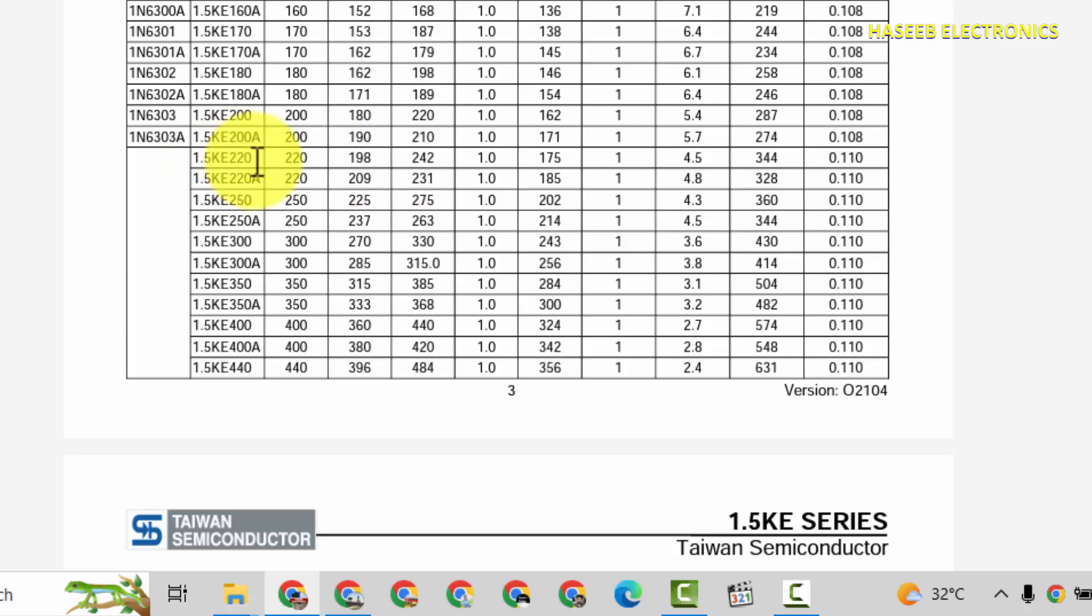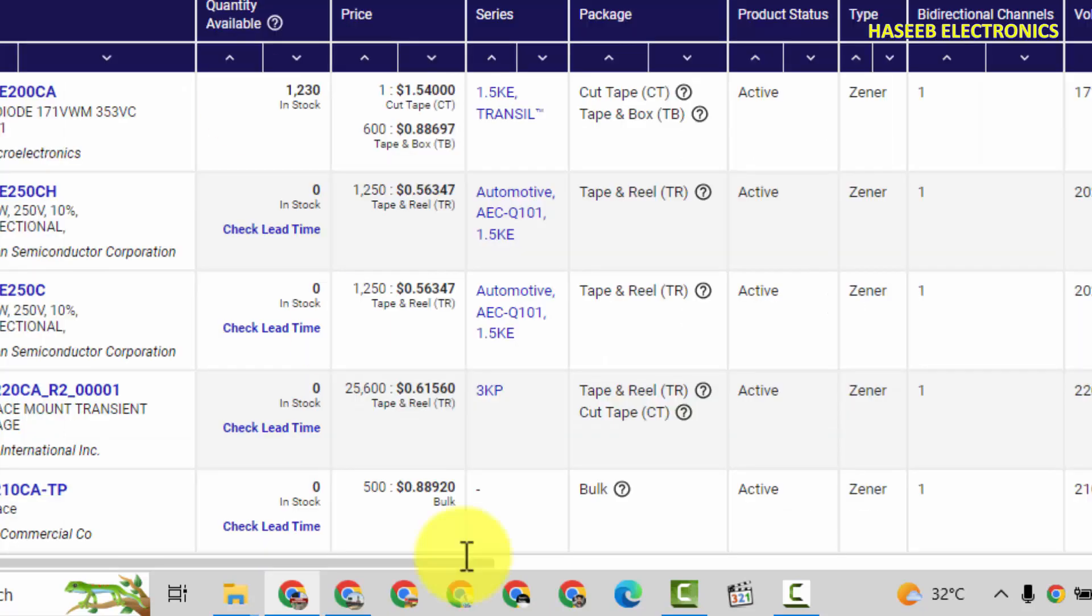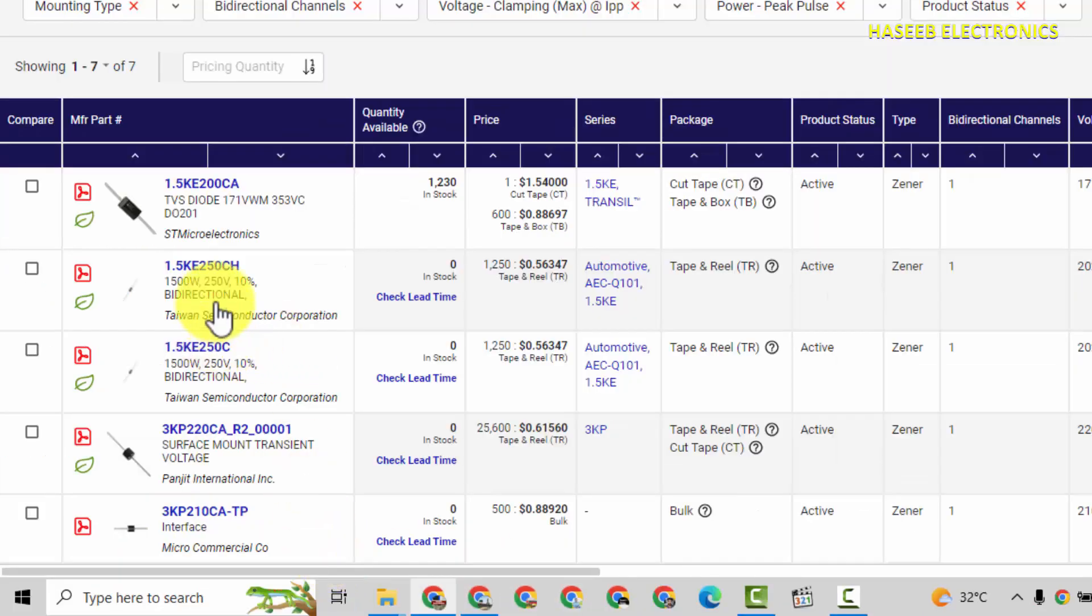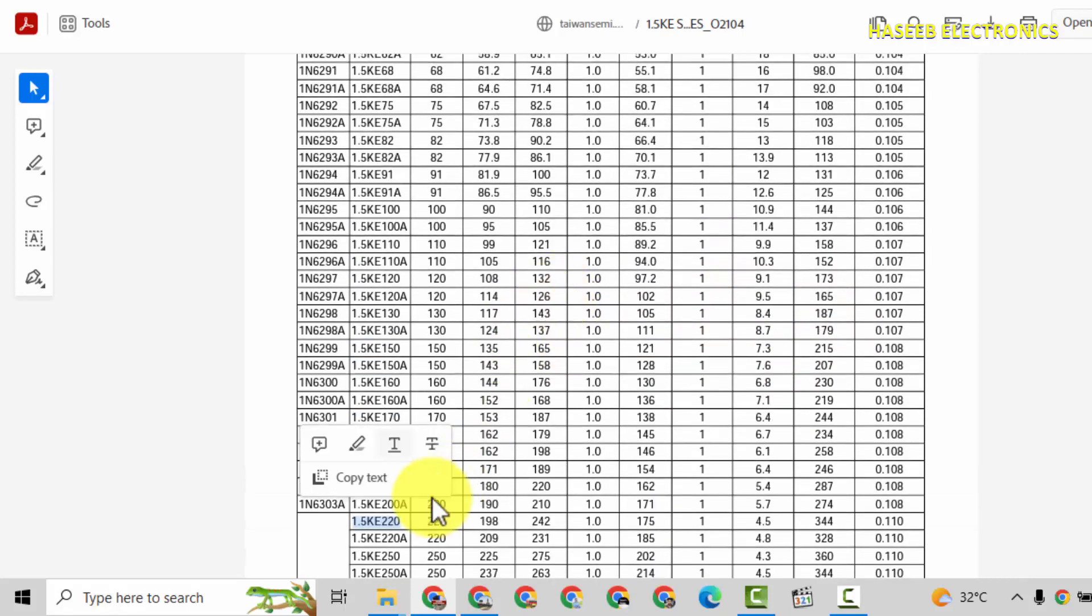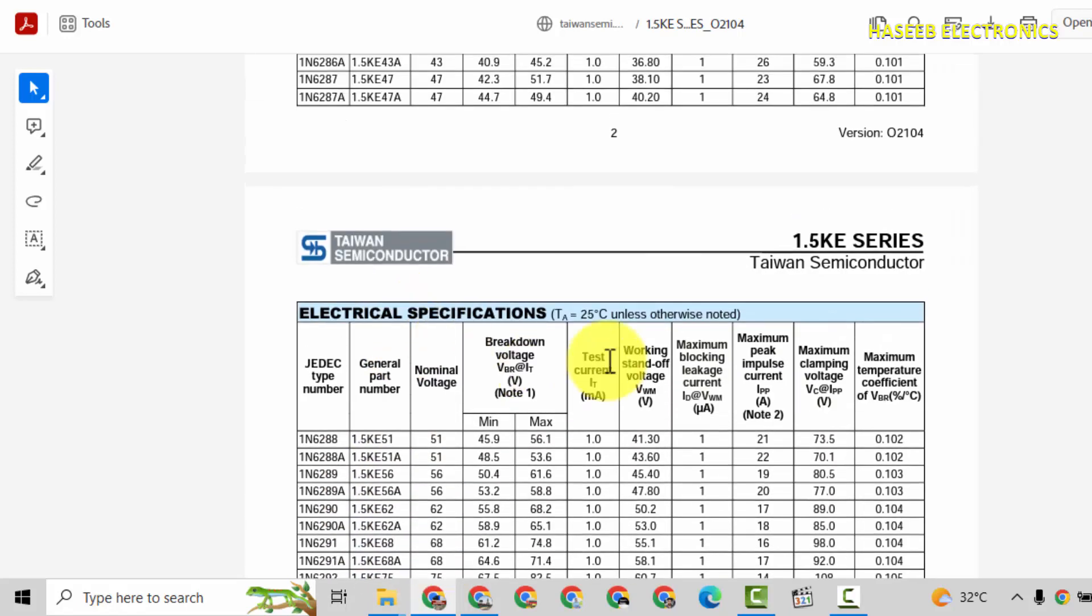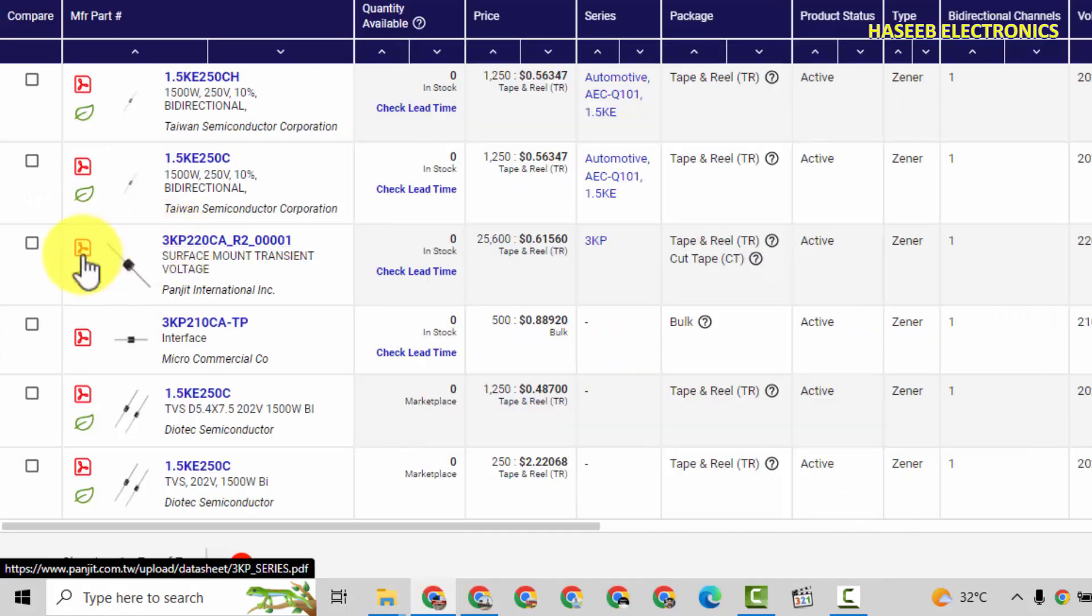KE220. 1.5KE220, that is best fit component for our requirement. And 250, that have also 360V clamping voltage. It has 1500W. If we select 3000W, it is 3000W.